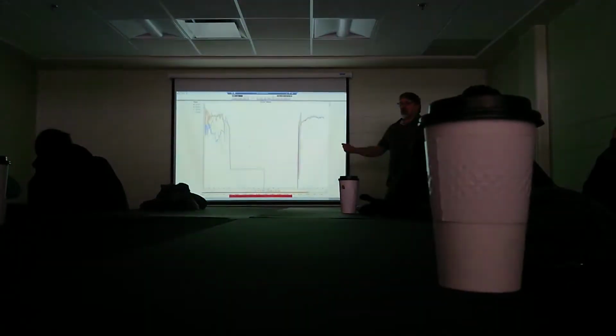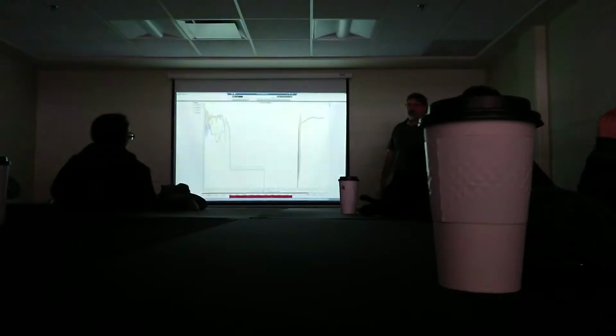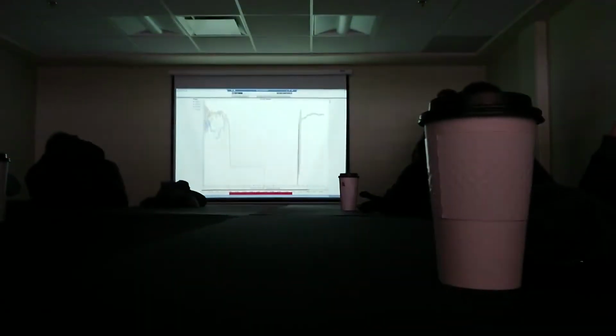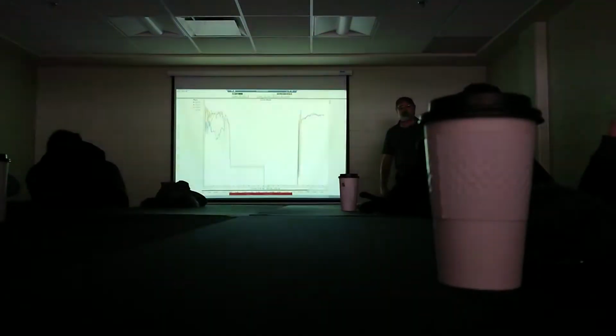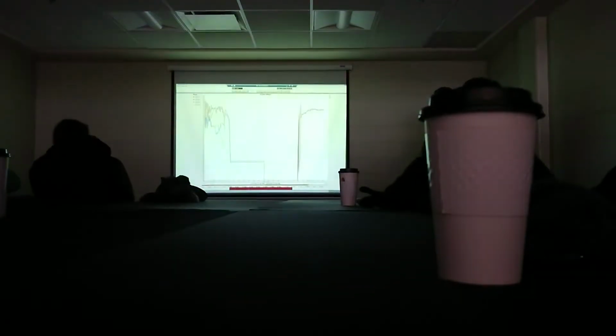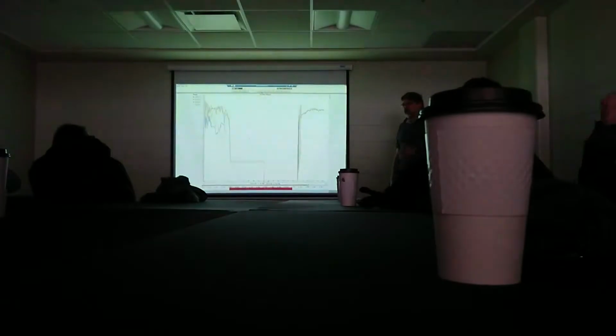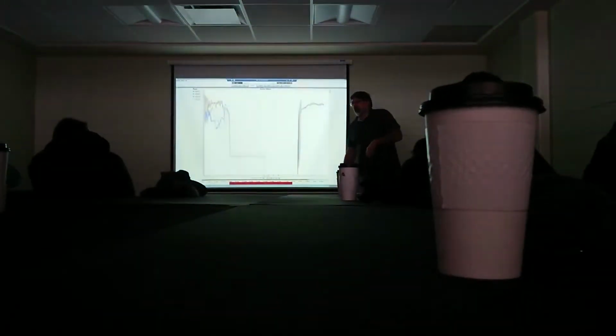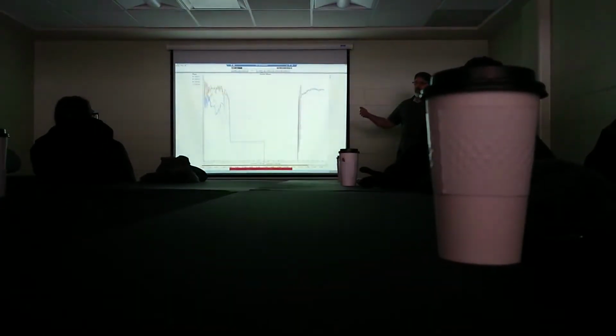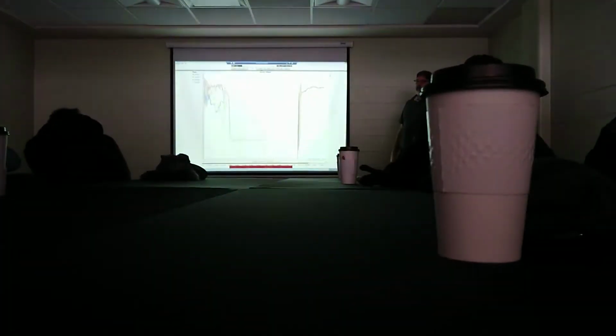Was there a safety lockout when we went in there? Yeah, as soon as you open the doors, because of the high current in there, it disengages the battery. The voltage isn't that big a deal, it's only around 96 volts DC, but the current is the huge changing factor. So opening either panel, doesn't matter which one, disengages the battery. That's what that is.